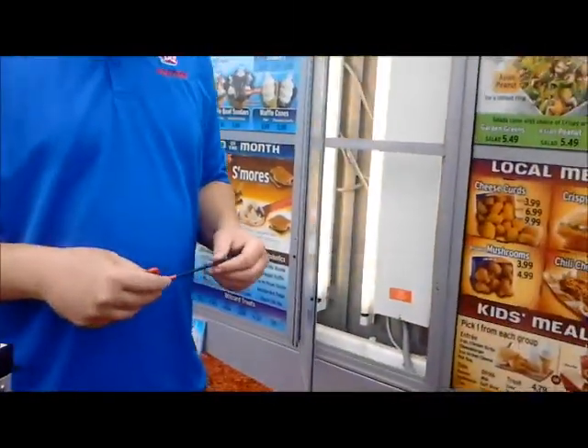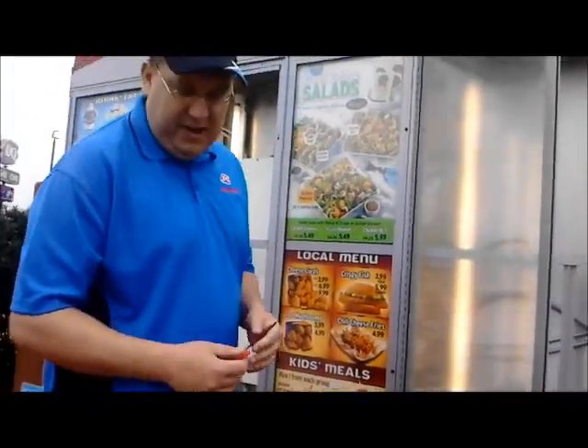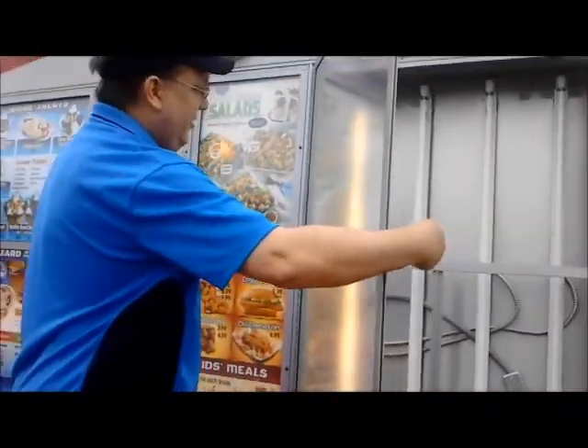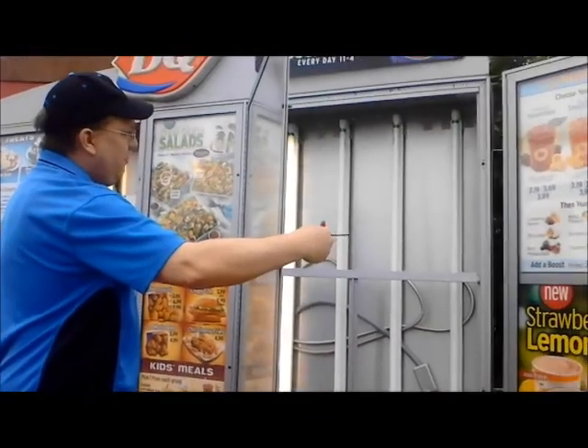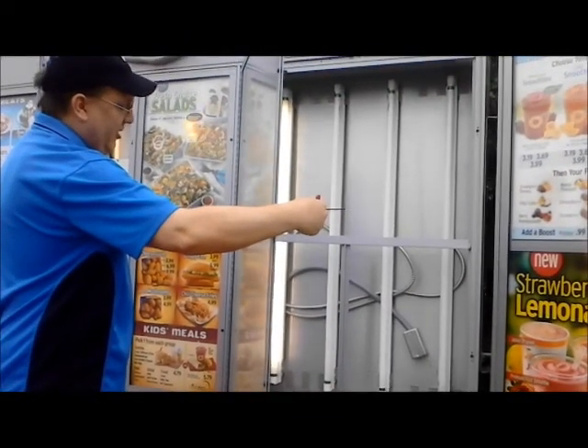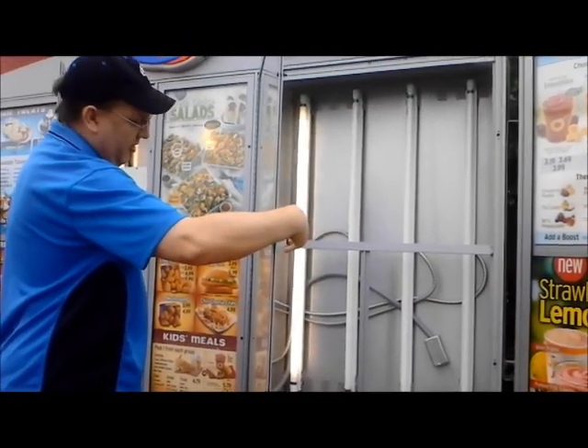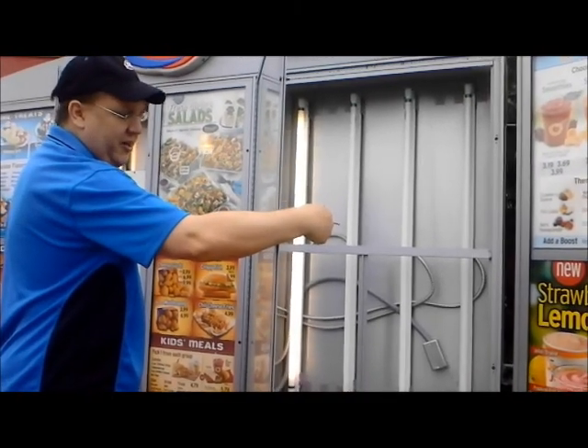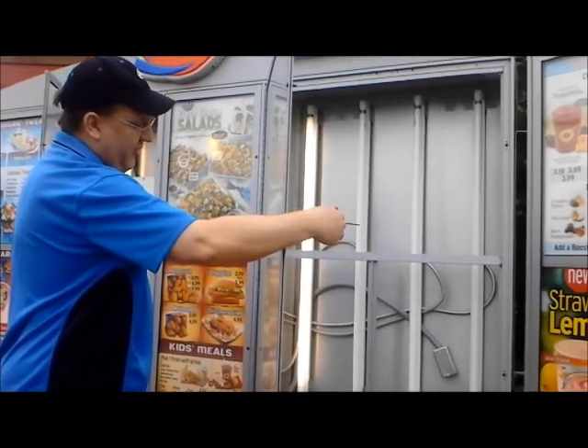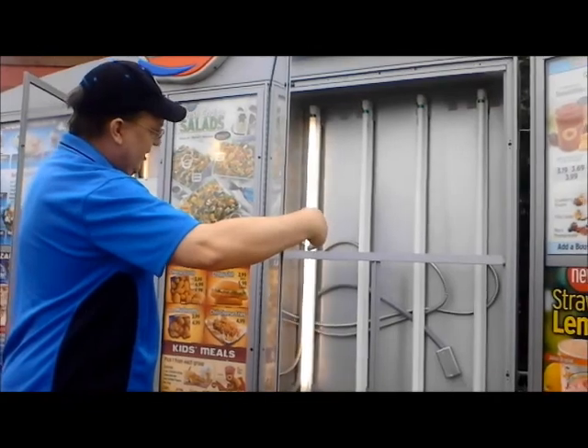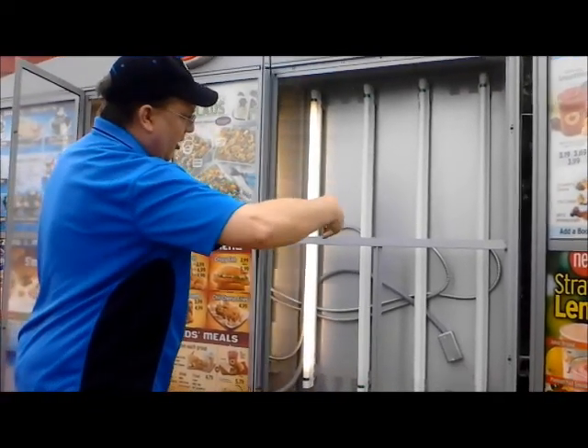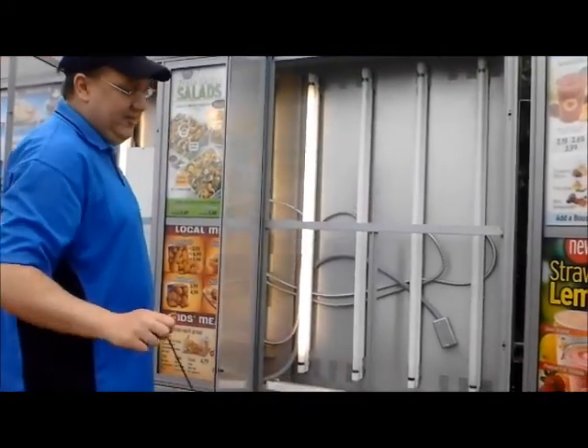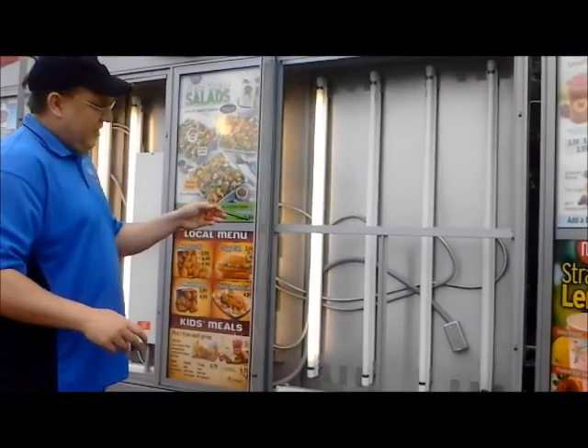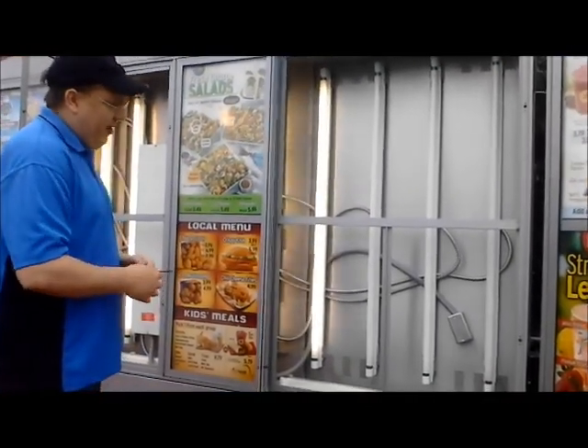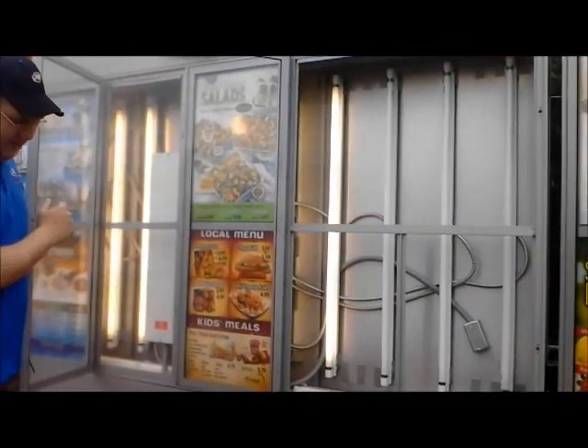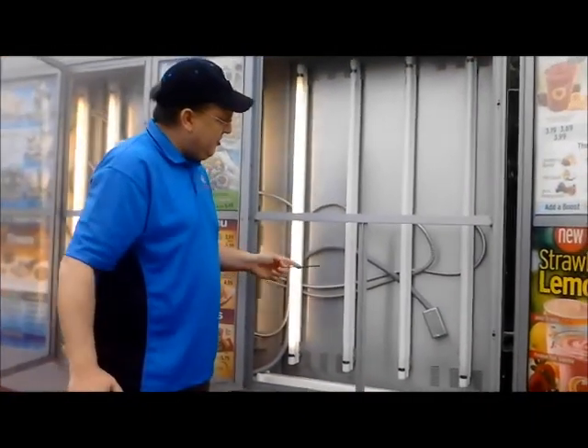Now, the first thing: I took the menu panels out already. As you can see on this side here, we got 3 bulbs out and they're not burned out. One of the best ways to test is to take one of your working bulbs and switch it with a bulb that doesn't work. If your working bulb doesn't work, then you know it's a ballast. I already switched this bulb and that bulb this morning, and even though it was lighted here, it wasn't lighted there. So we definitely have ballasts out here, at least 1, maybe 2.